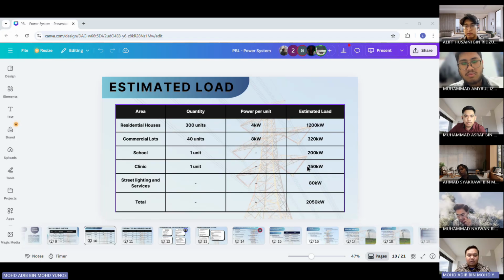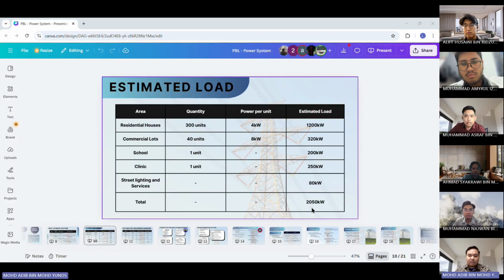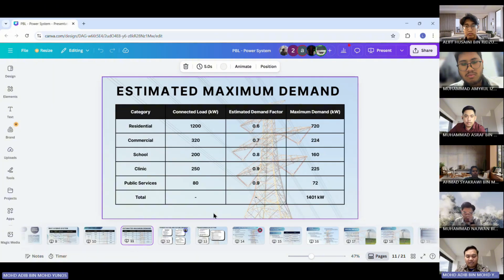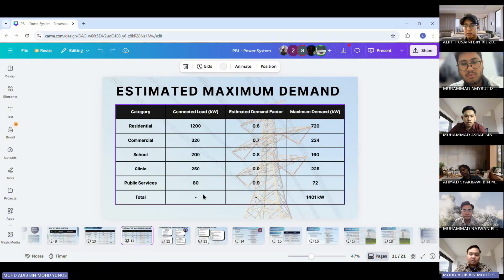However, sizing our transformer for 2050 kilowatt would be over-engineering. It wastes capital and increases core losses. So per standard practice, we apply an estimated demand factor. This brings us to the real number, which is the maximum demand. For the residential area, we apply a factor of 0.6, assuming standard domestic diversity, and not everyone cooks and showers at the same time.